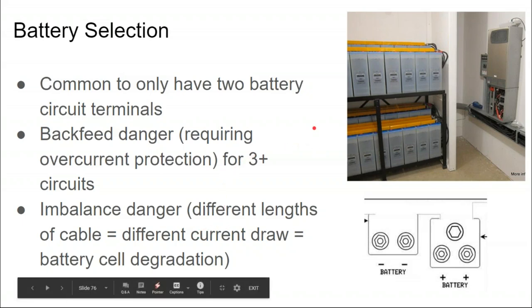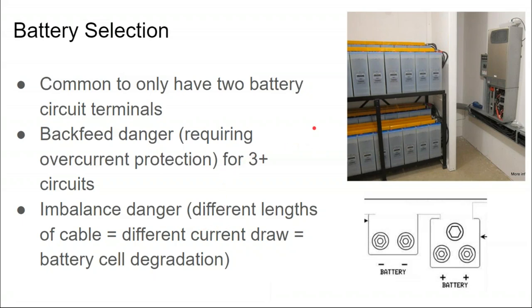Best practice when sizing batteries is to have no more than 2 battery circuits per battery inverter. I, in fact, prefer 1 battery circuit per battery inverter, just due to the differences in lengths between the top battery circuit and the bottom battery circuit on how they loop back into the battery inverter.